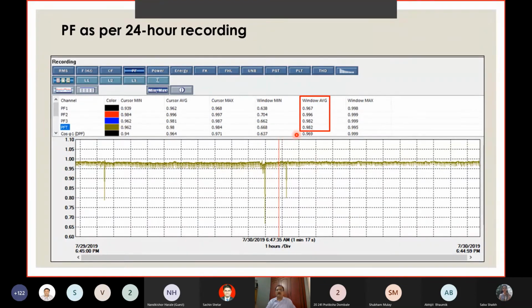So for this 24 hours, the average power factor was 0.982, although the power factor reached 0.995. Occasionally, the power factor was down. See, for example, here, minimum is 0.68, 0.70. So these are the reasons why the average is pulling down from 0.995. So one has to understand which are those loads whose infrequent usage is actually causing the drop in power factor, and accordingly manage this. So when you deal with the customer, you should be able to highlight this information and educate the customer to undertake measures such that this value will also be reasonably high, 0.95, 0.96, so that this will become 0.995.